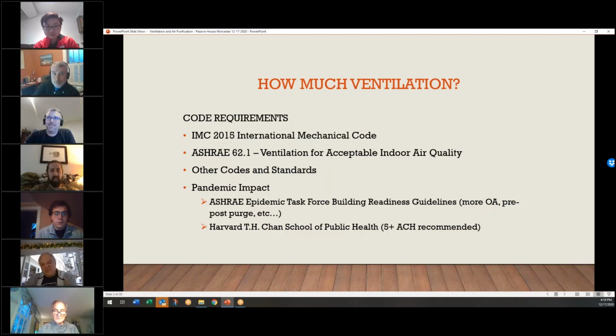But again, so ASHRAE recommends a lot more outside air, and pre and post purge, basically ventilating the building, putting it in an occupied mode 2 to 3 hours prior to occupancy and 2 to 3 hours after occupancy, to flush the space out with as much outside air as you can.